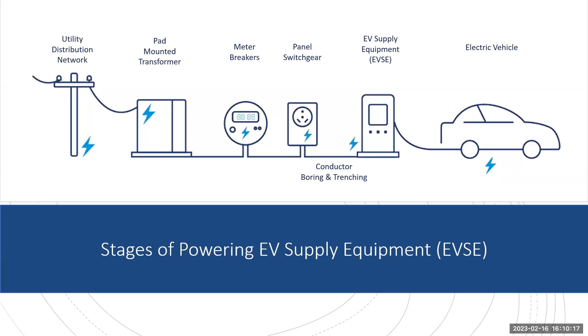Then you have to install other things like primary or secondary metering as required by the customer on site, a main breaker, and distribution switchgear to distribute power from 480 volts down to each individual rectifier connected to each charge point, or integrated rectifiers at the charge points or level 2 chargers. If you look at all these steps, I count at least 6, and there could be many more.